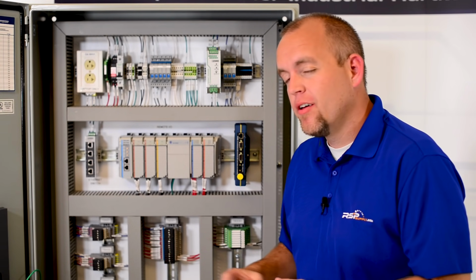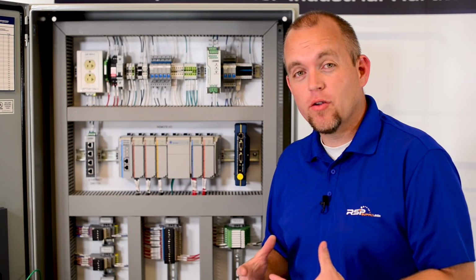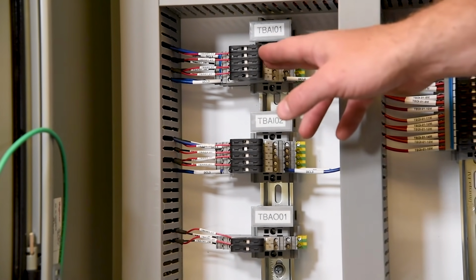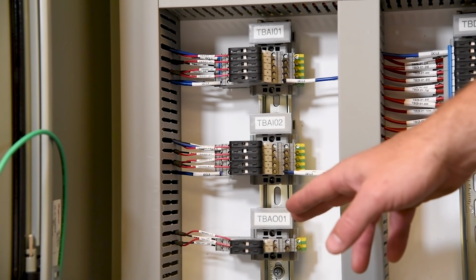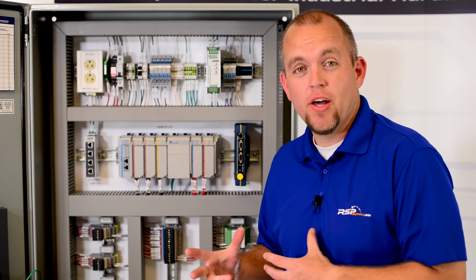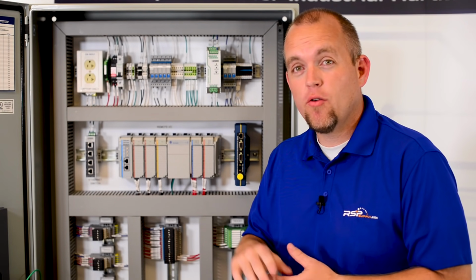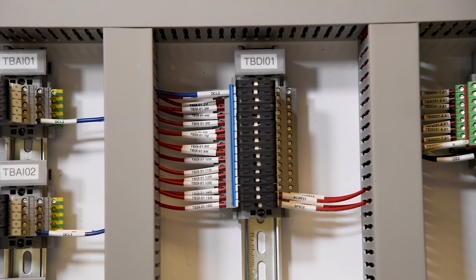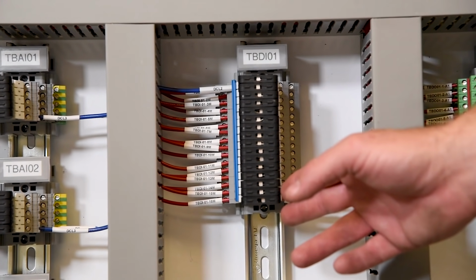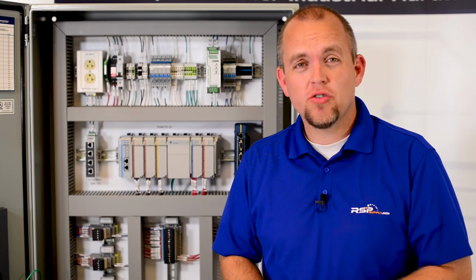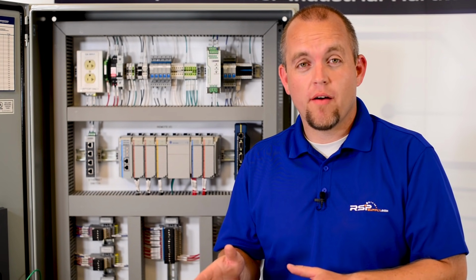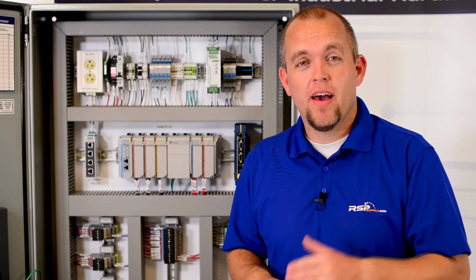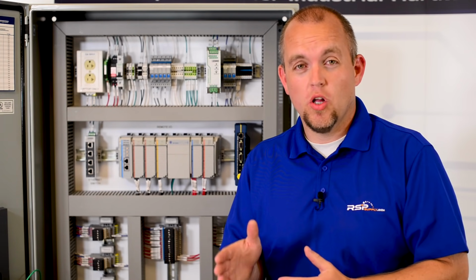Depending on the instrument, we have varying types of signals. Here we have our analog signals. Analog signals measure a range of values, such as a tank level or water pressure. Here we have the terminal blocks that measure our digital signals. Digital signals are either on or off. An example of this might be a valve is either open or closed.